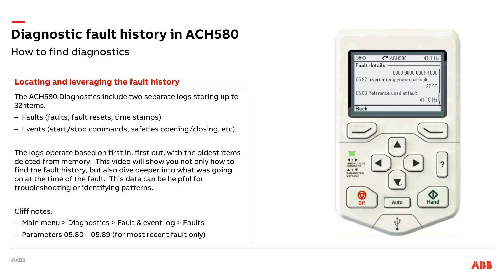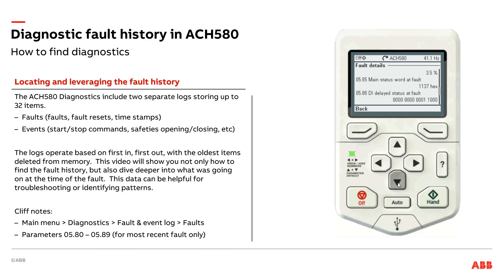We've got our speed reference — this is how fast we're being told to run at the time of fault. We were being told to run at 41.1 Hertz, and as we looked at earlier, we were at 41.09 Hertz — basically at set point. And lastly, I can see the Main status word at fault. I've got a bunch of zeros and ones here, reading right to left. Sometimes I feel like I'm Neo in the Matrix reading all the ones and zeros coming down the screen.